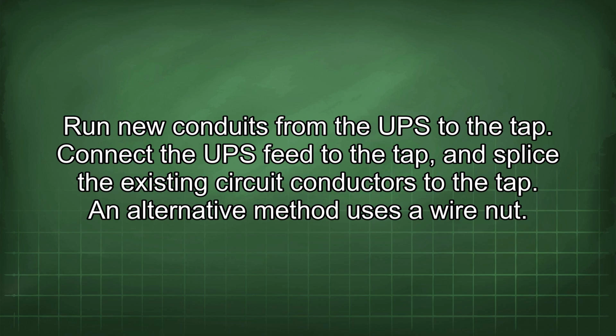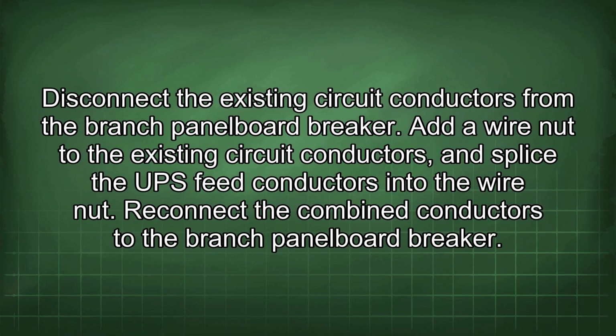An alternative method uses a wire nut. Disconnect the existing circuit conductors from the branch panel board breaker. Add a wire nut to the existing circuit conductors and splice the UPS feed conductors into the wire nut. Reconnect the combined conductors to the branch panel board breaker.